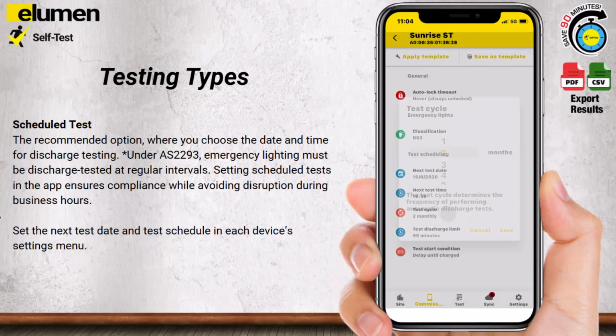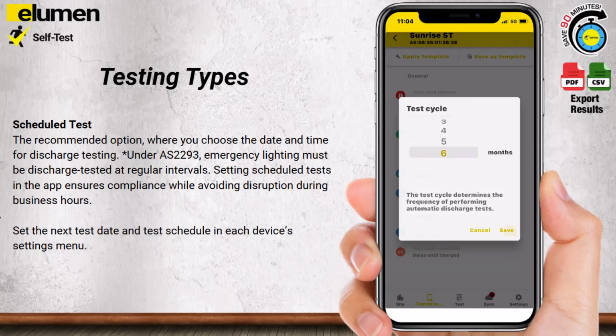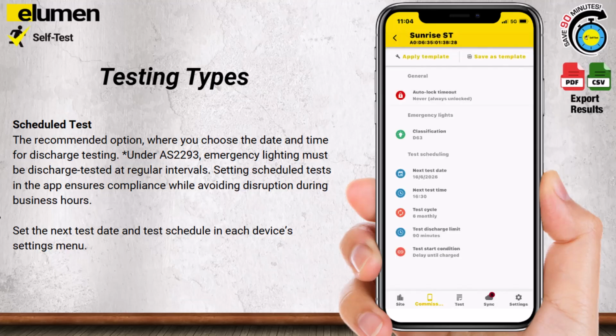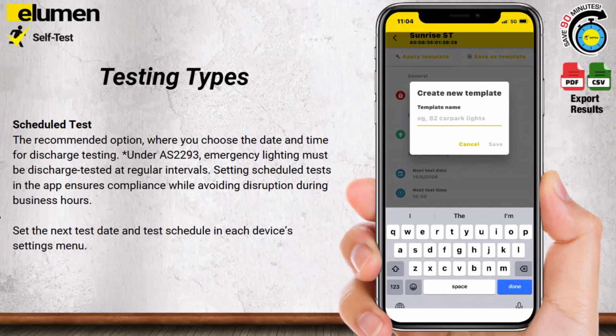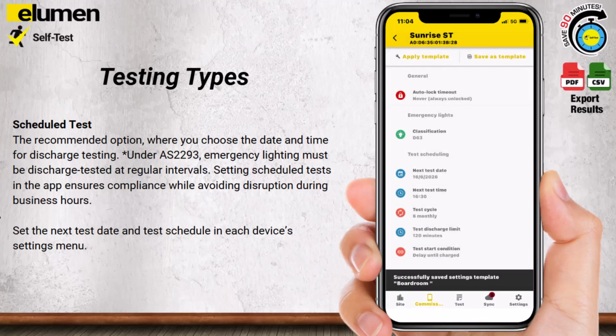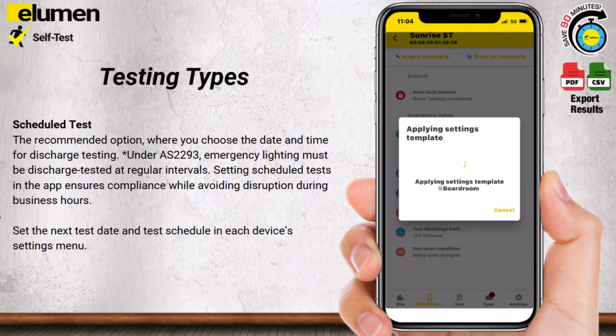It's important to remember, factory defaults may trigger a test at the time of installation. If new devices are added without reconfiguring, their schedules may be out of sync with the rest of the site. This could cause multiple fittings to test at random times, creating confusion for building occupants and making maintenance harder to track. To avoid this, always configure new fittings so that their test cycles align with existing site assets.